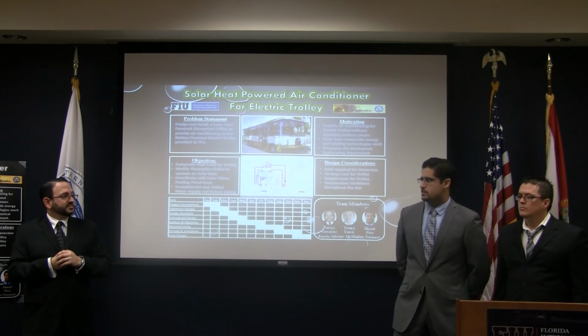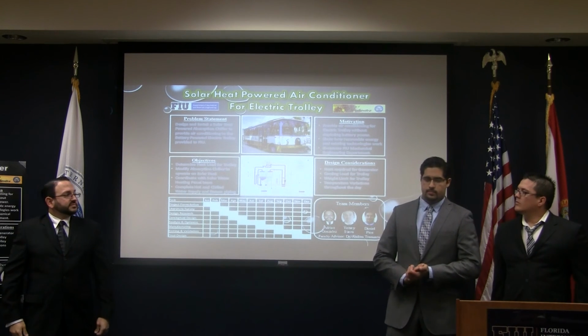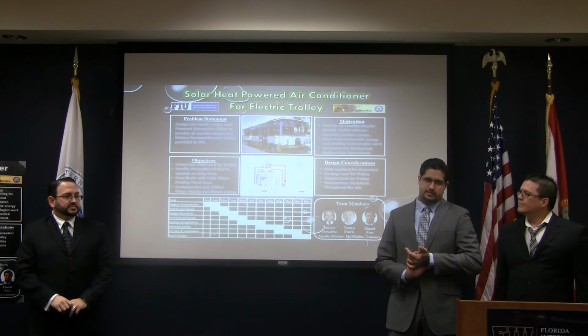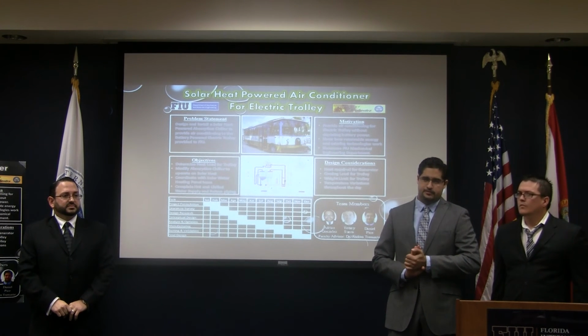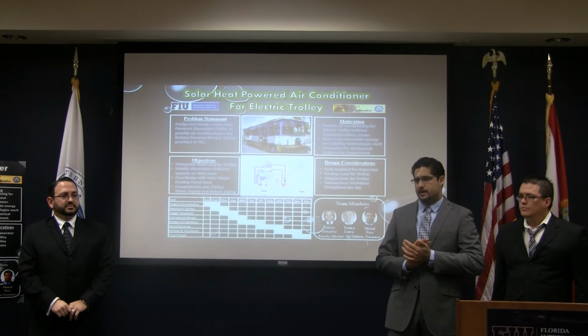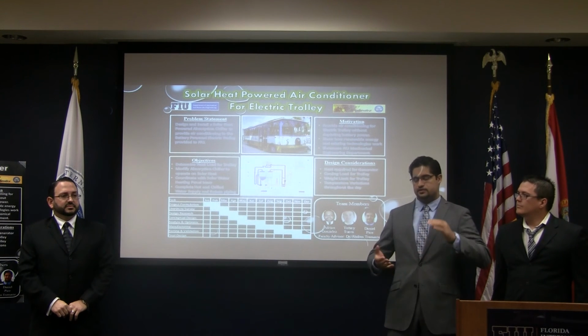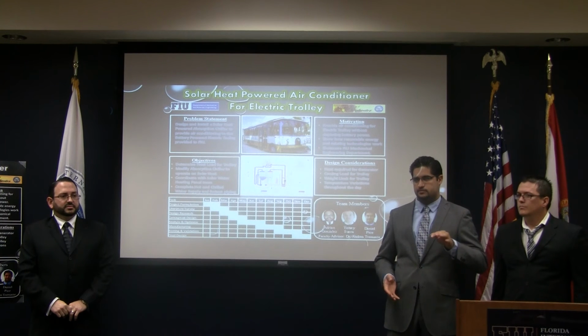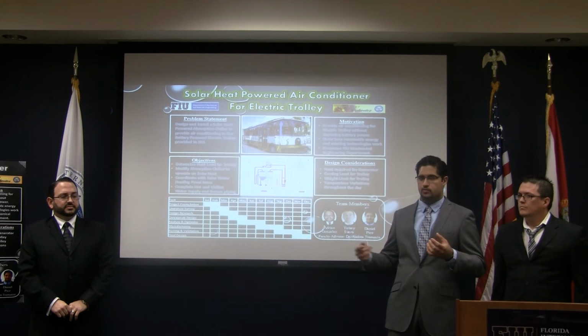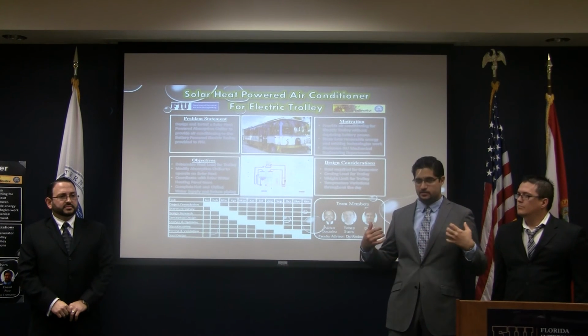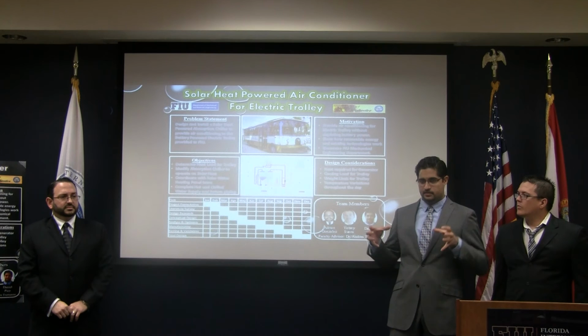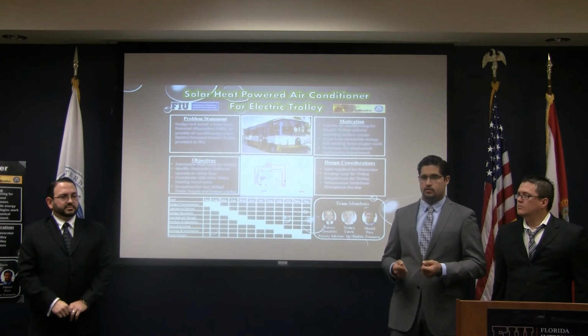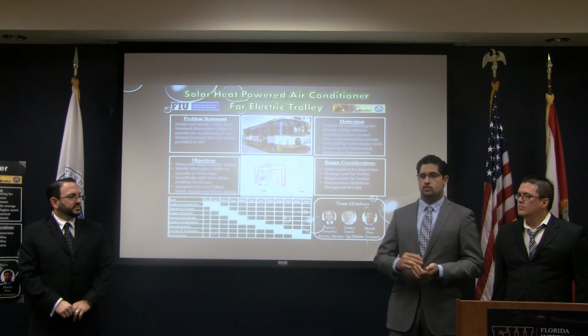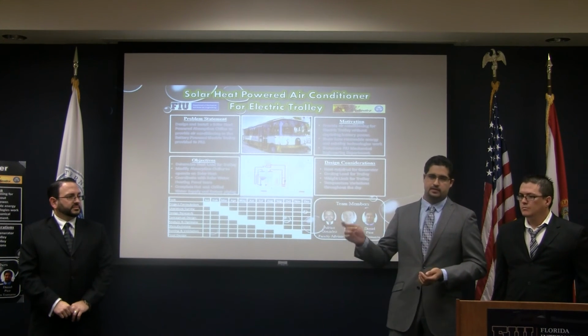Just to add a couple points to that: the first thing we need to do is determine the size of an interfacing coil, which is why there's been very little analysis so far. First we have to tear down the machine. There's only a certain portion referred to as the generator in an absorption chilling unit, where the burners are lined up around the pressure vessel into which the ammonia water solution is pumped. It's completely sealed off, but it's direct heat, fire hitting the outside of the vessel. Our idea is to remove that from around the generator and determine the proper dimensions for a coil that will receive hot water from the solar collector and circulate it.